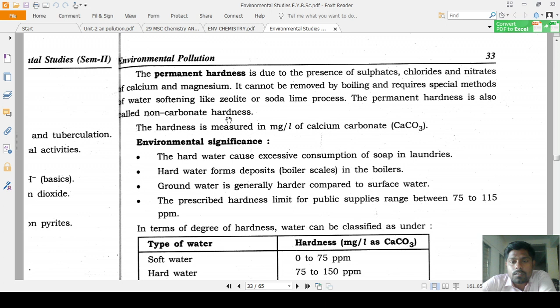Now, what is the permanent hardness? Permanent hardness is due to the presence of sulfates, chlorides and nitrates of calcium and magnesium, and it cannot be removed by boiling, but it requires special methods like water softening, like the zeolite or soda lime process. The permanent hardness is also called the non-carbonate hardness. Hardness is measured in milligram per liter of calcium carbonate.